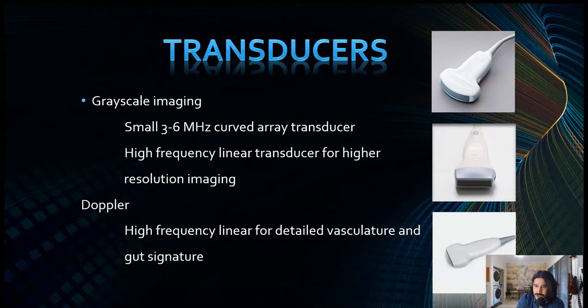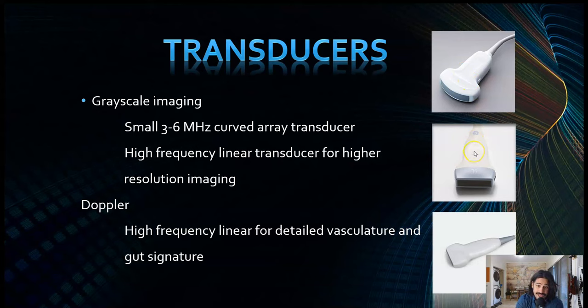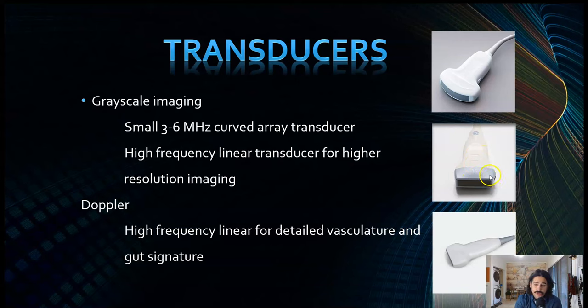The transducers we use are just like any other abdominal application. Primarily for the upper abdomen, especially if you want to include organs like the pancreas and liver, you're going to use the curved probe. The ones I like to use most for gastrointestinal ultrasound is the linear, especially the 9L. This is very good for appendix, cecum, colon, small bowel, and looking for free fluid. On smaller or slimmer patients, you could even use a 15 megahertz linear transducer and get really nice pictures.